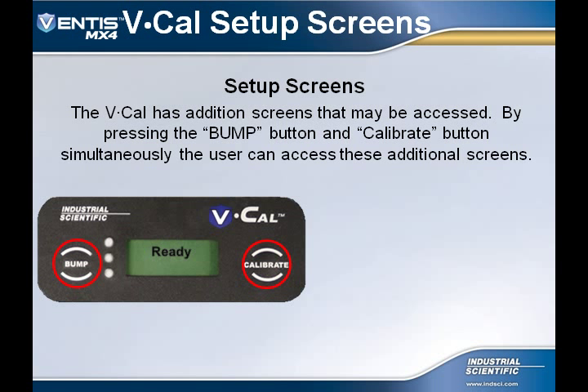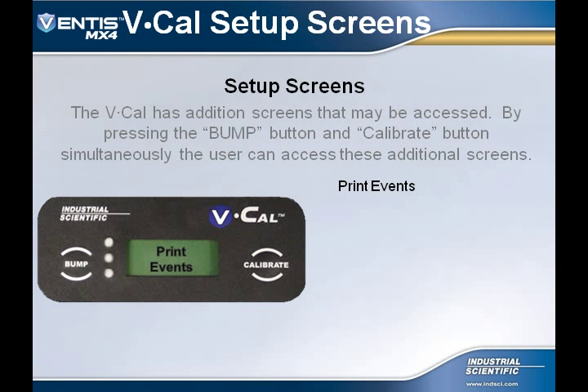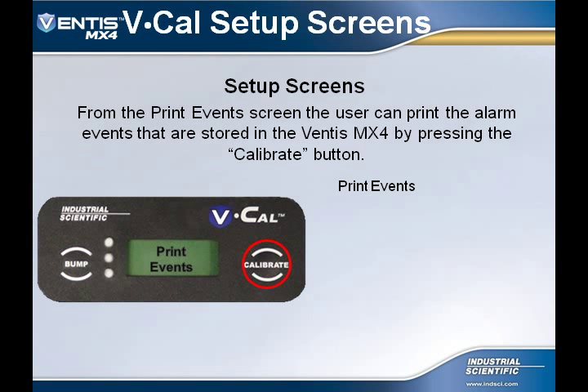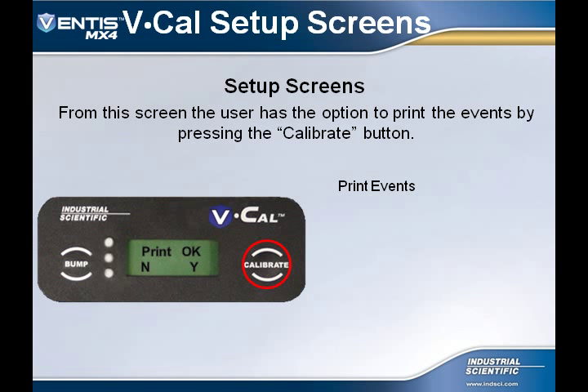Now we'll take a look at how to set up the VCal. By pressing the bump test button and the calibrate button simultaneously, the user can access these setup screens. The first of these screens is the print events. Pressing the calibrate button will allow the user to print the 15 alarm events that are stored in the Ventis MX4 that is docked in your VCal. From this screen, pressing the calibrate button will initiate the printing of the 15 events.